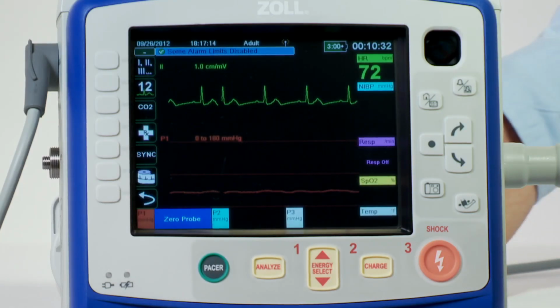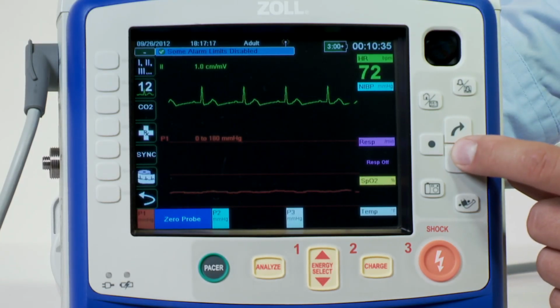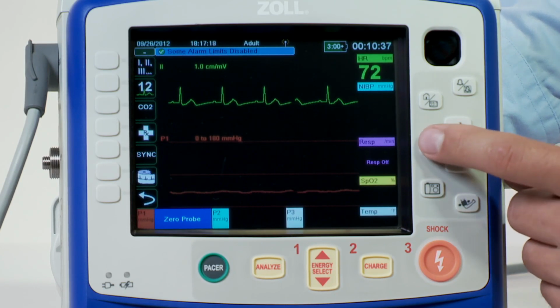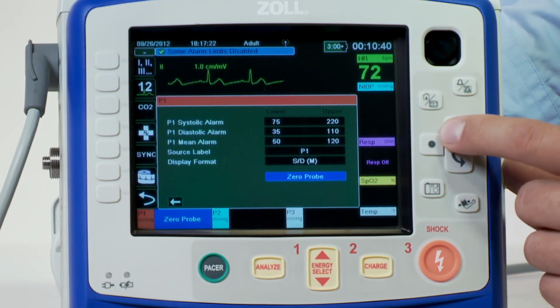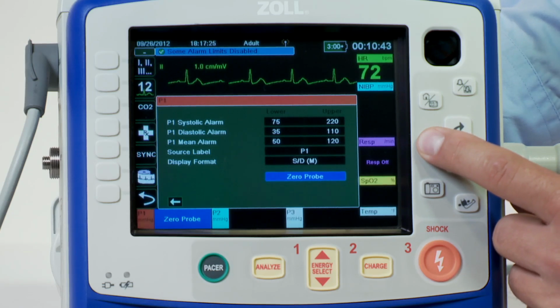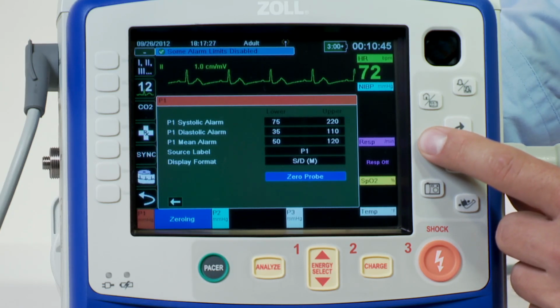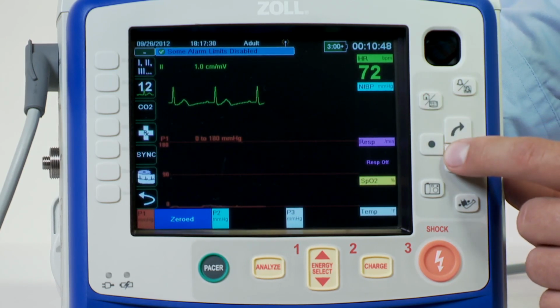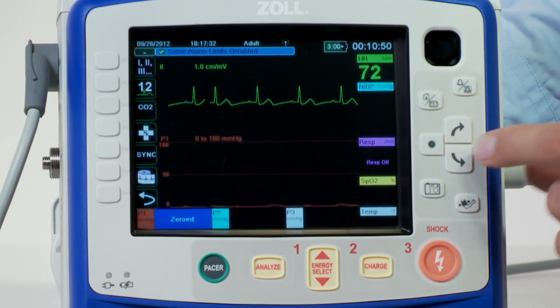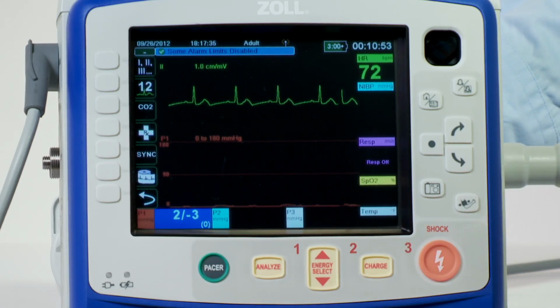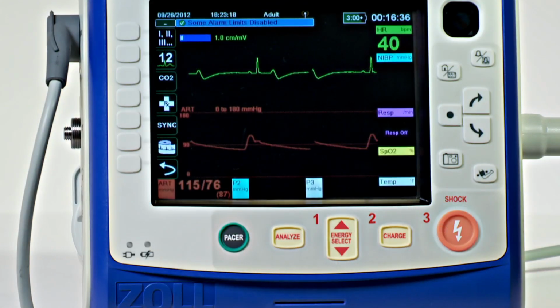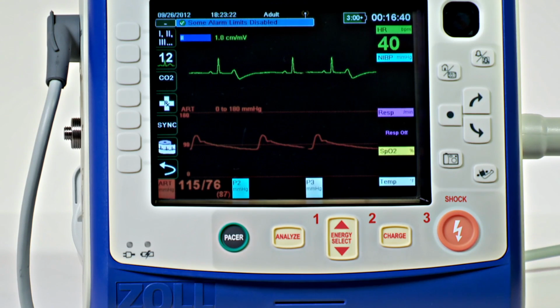Use the navigation keys to highlight and select the transducer's IBP channel and display the IBP channel's parameter control panel. Select Zero Probe. The unit displays the message zeroing in the IBP channel's numeric display. The message zeroed appears in the IBP channel's numeric display. Close the transducer's stopcock. You can re-zero a transducer at any time by opening the transducer stopcock to atmospheric pressure. If the unit accepts the new 0 reference value, the unit displays pressure values that are based on that value and adjusts the waveform accordingly to the new scale.